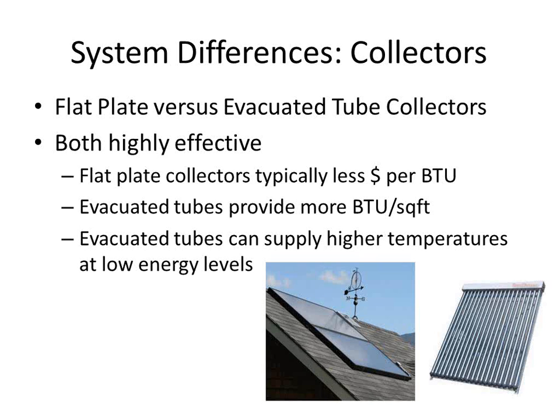However, a lot of proponents say evacuated tubes are more efficient, and they do produce more BTUs per square foot. So if you're limited on the amount of space you have on your roof to work with, or you're really trying to produce an awful lot of power, so it's getting expensive to build racks and things like that, an evacuated tube system is going to produce more BTUs per actual square foot of collector area. Evacuated tubes also can supply higher temperature levels at lower energy levels. Since they're evacuated, as the absorber gets hot, you're not going to lose as much heat through convection, particularly when it's very, very cold outside.